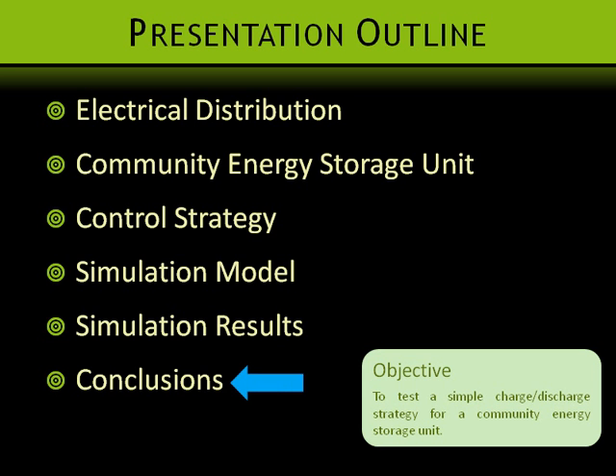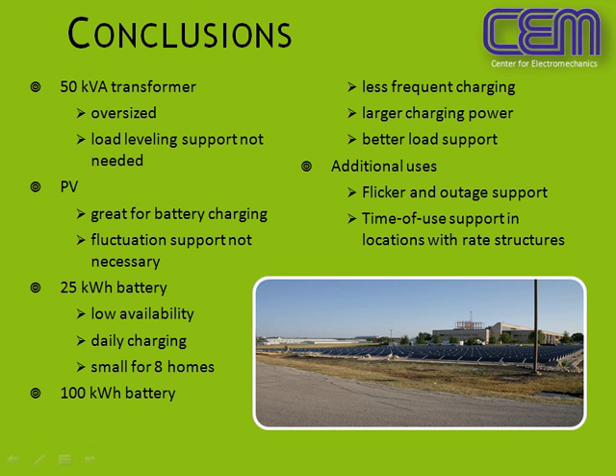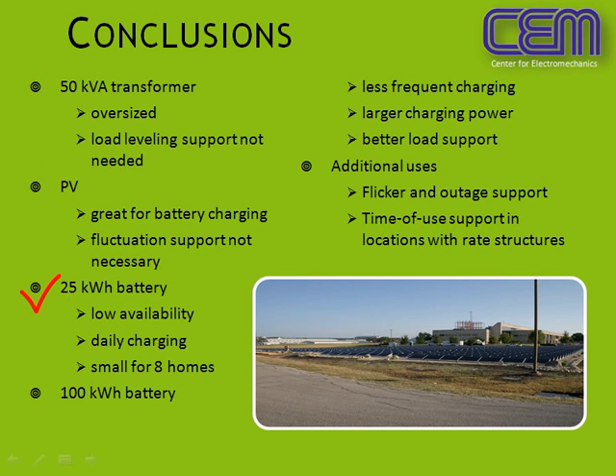Finally, we present the conclusions of this study. The 50 kVA transformer is sized properly for the 8 homes shown in this study, meaning that a storage unit is not needed for transformer load leveling at this particular community. The PV unit is an excellent source to charge the battery. However, the battery should not be used to support PV fluctuations, because such small PVs do not produce system instabilities when supported by the grid, and the battery would be discharged too early in the afternoon. On the battery size, the 25 kWh battery appears to be small for the given load as it discharges quickly, but this is a function of the control strategy which is being revisited.